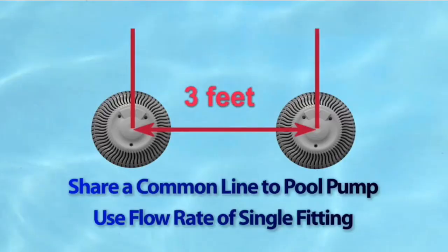We've already handled flow rate and all of that, sump depth and all that previously. So if it's blockable, it's a single drain, yes. Is it blockable? No, then go to the next section. Then is it a multiple drain system at least 3 feet apart? So under the federal law, if you've got dual drains, but they're closer than 3 feet, then you have to treat it like a single drain and go to a backup system.